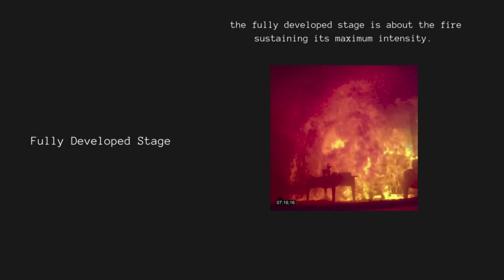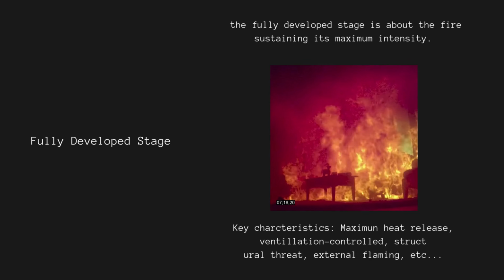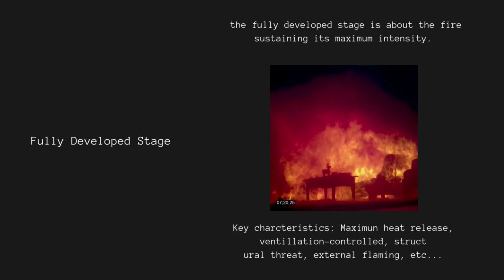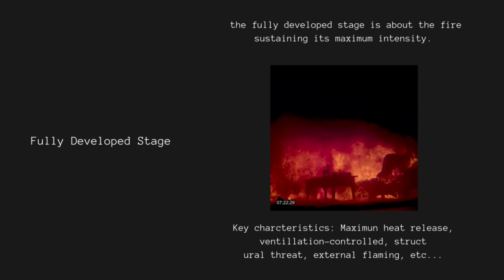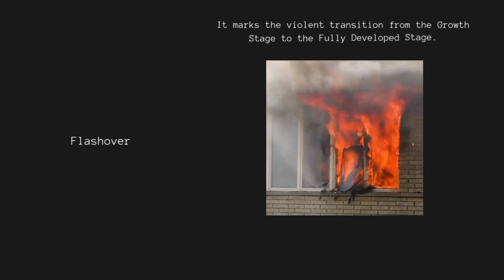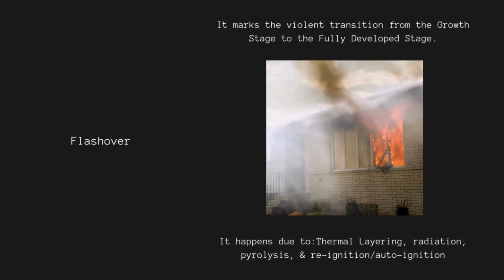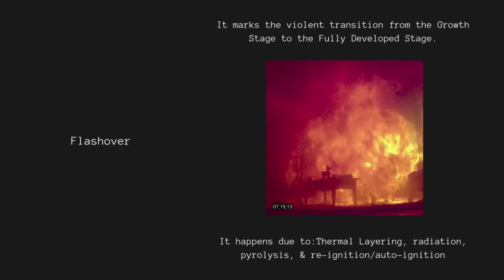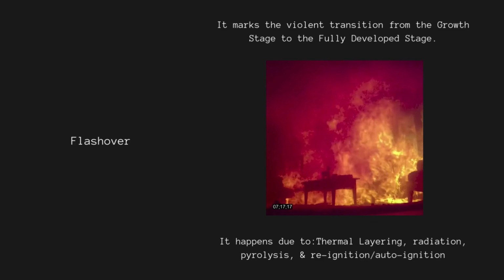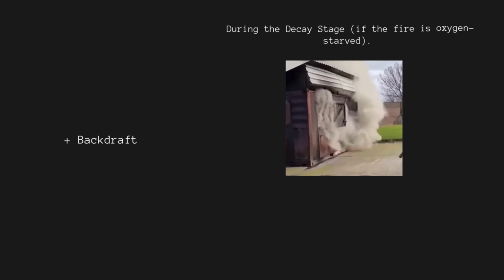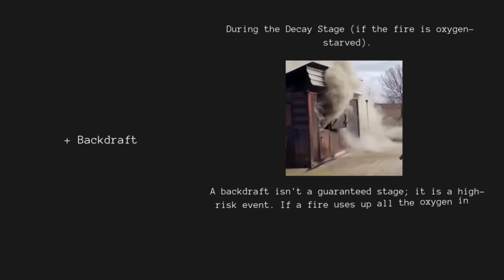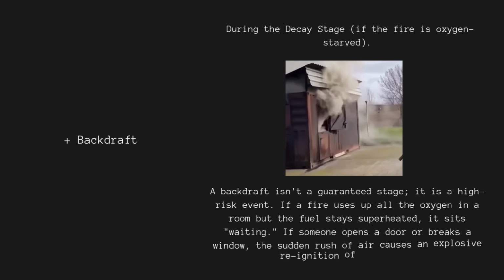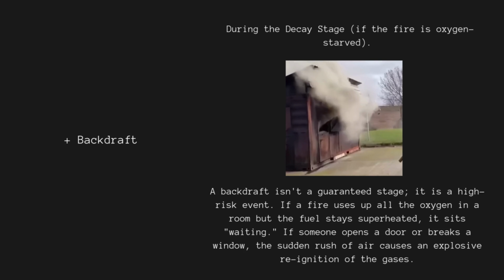The fully developed stage is the peak of the fire's intensity. All combustible materials in the compartment have ignited and the fire is consuming the maximum amount of fuel possible. Flashover is the simultaneous ignition of all combustible items in a room due to extreme radiant heat. It marks the instant transition from a growing fire to a fully developed one. Understanding the science behind the fire triangle contributes to acknowledging events such as backdraft and how sudden introduction of oxygen, such as opening a door, can lead to detrimental events.